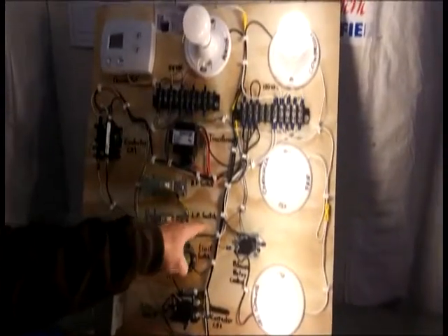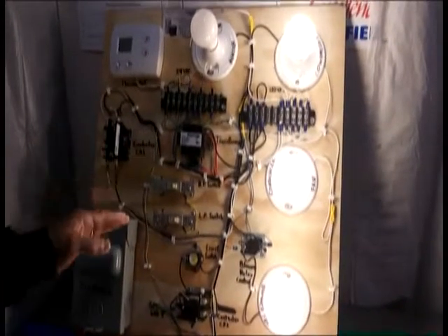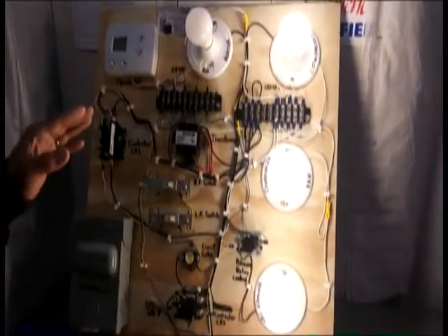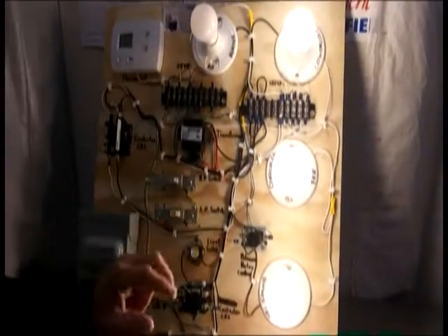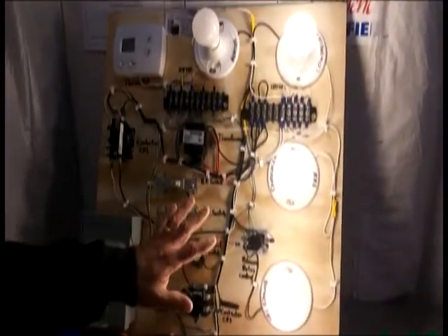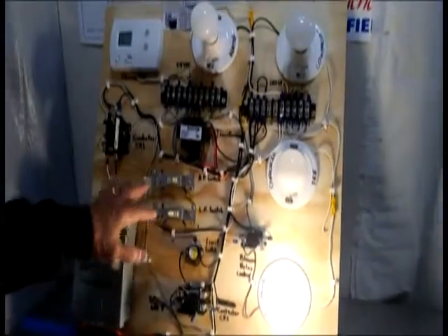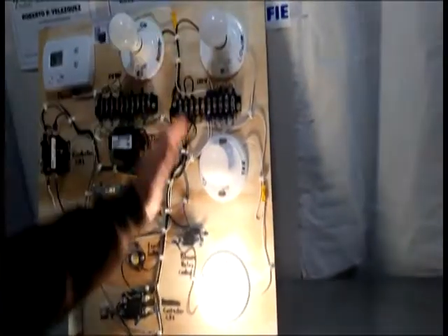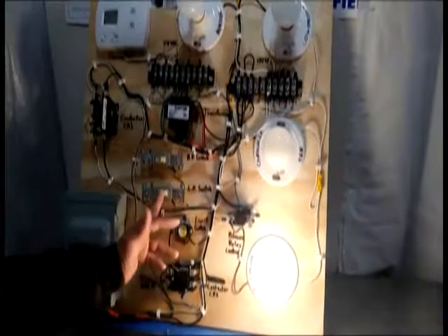And the same thing we have, because they're connected in series, those two switches, the low pressure switch. For instance, the low pressure switch is coming low in the refrigerant, so maybe they have a leak, low in the refrigerant, something that can cause the low pressure. When the low pressure is too low, this is going to be off, and the compressor is off, and the condenser fan motor is off, and the blower is still running. So let's say we add more refrigerant, for instance, so this is going to be on, and then this is going to be working.